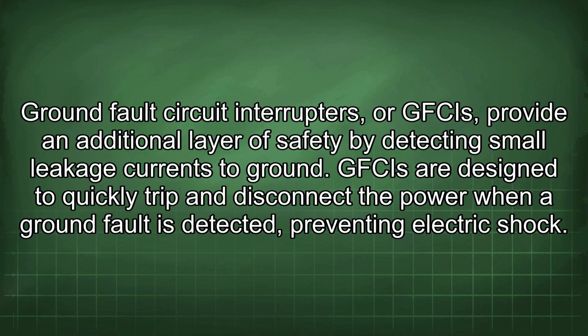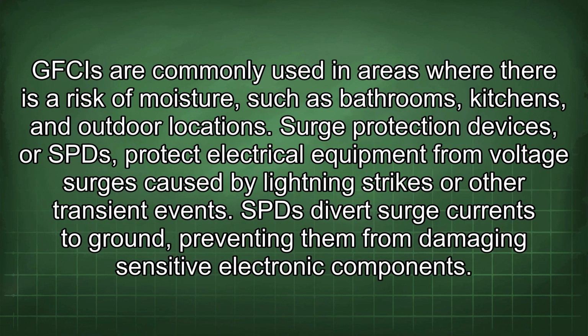Ground fault circuit interrupters, or GFCIs, provide an additional layer of safety by detecting small leakage currents to ground. GFCIs are designed to quickly trip and disconnect the power when a ground fault is detected, preventing electric shock. GFCIs are commonly used in areas where there is a risk of moisture, such as bathrooms, kitchens, and outdoor locations.